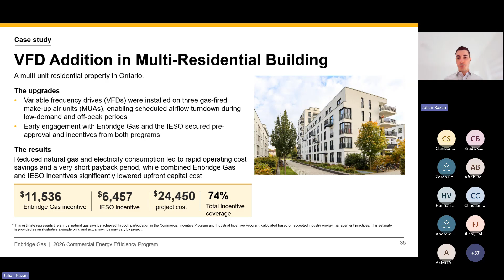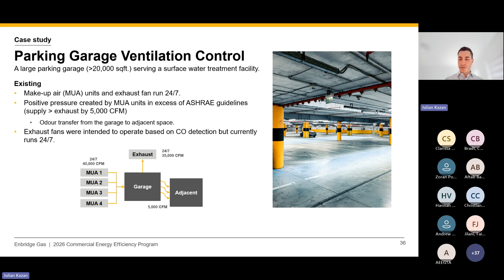And this is the last ventilation project I'll talk about, the second last case study I'm going to go into. But I kind of want to give you guys some idea of how we do the calculations, right? And kind of what we're looking for when we go to site and some of the data collection that we're doing. So in this example, there was a parking garage where they had CO detection, but either it was shut off or not working. So they're essentially ventilating 24/7, 40,000 CFM of fresh air all the time into this garage, over-ventilating it, running when it's not supposed to, right? So this is low-hanging fruit to me, an easy energy project we should be doing.